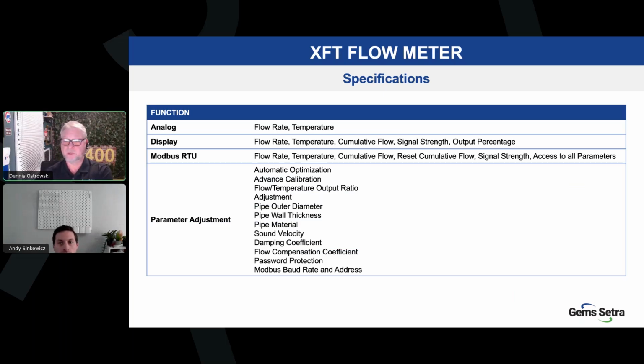We have a list of the parameter adjustments that are available. Automatic optimization is kind of like an auto tune feature. So after you've commissioned the device, an auto tune would normally get it working. Again, there may be advanced calibration that is necessary. There are about 10 different calibration adjustments in the device so that you can fine tune it to your application to get the accuracy and the consistency that you need. But you see, all those parameter adjustments are available. You don't need Modbus to do it. You can do it right there with the keypad as well. So that's all stuff that's available at your fingertips.